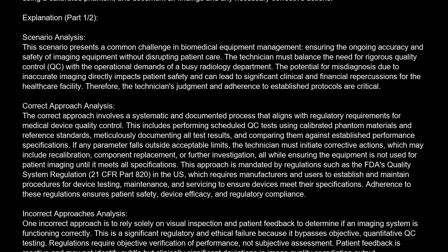If any parameter falls outside acceptable limits, the technician must initiate corrective actions, which may include recalibration, component replacement, or further investigation, all while ensuring the equipment is not used for patient imaging until it meets all specifications. This approach is mandated by regulations such as the FDA's Quality System Regulation, 21 CFR Part 820, in the U.S., which requires manufacturers and users to establish and maintain procedures for device testing, maintenance, and servicing to ensure devices meet their specifications. Adherence to these regulations ensures patient safety, device efficacy, and regulatory compliance.